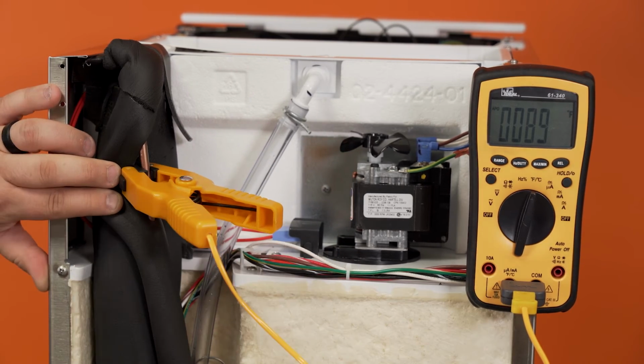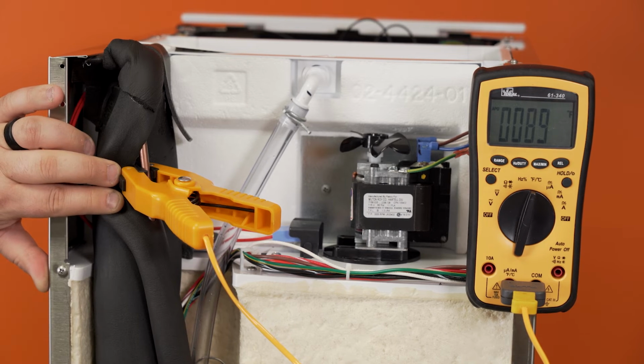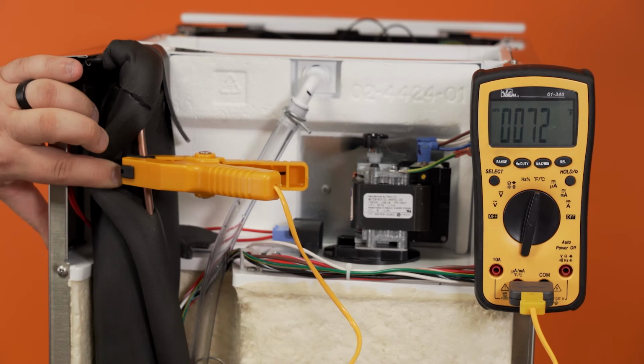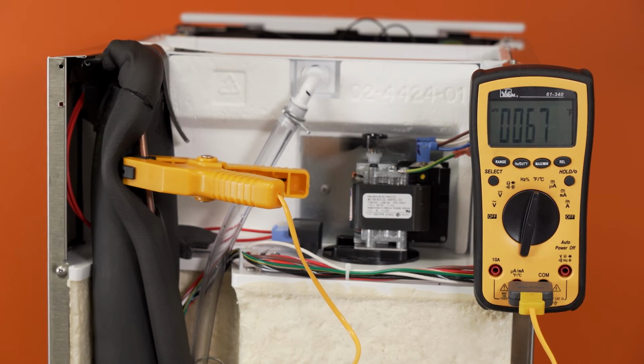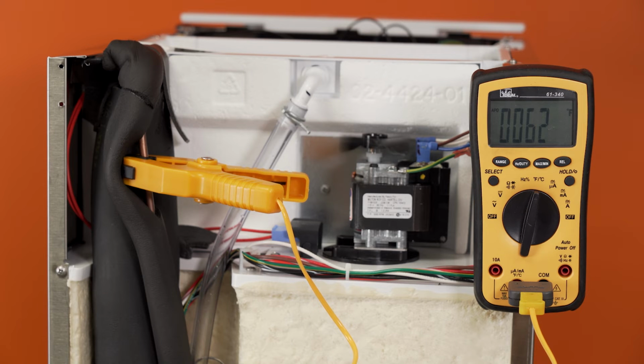A properly functioning valve should be open during harvest and should have minimal to no temperature drop across the valve. If there is a temperature drop across the valve of 5 degrees or more, this would indicate that the valve is not fully opening and should be replaced.